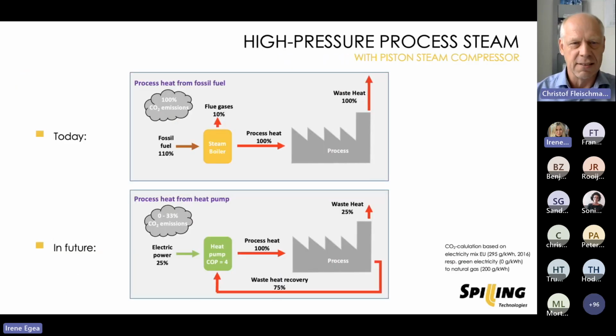Here in this slide, you see the idea of heat pump integration in industrial processes. The upper picture shows the situation as it is at many processes today. A fossil-fired boiler is supplying high-pressure steam process heat to a process, and most of the heat afterwards goes from the process into the atmosphere. So it's completely wasted. The idea of integrating heat pumps is shown in the lower picture: as much waste heat as possible from the process is recovered and lifted from the lower temperature level where it's normally available to a higher temperature level with a heat pump, to supply it again in the quality the process heat is required.